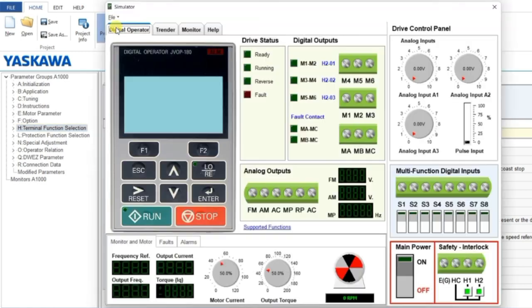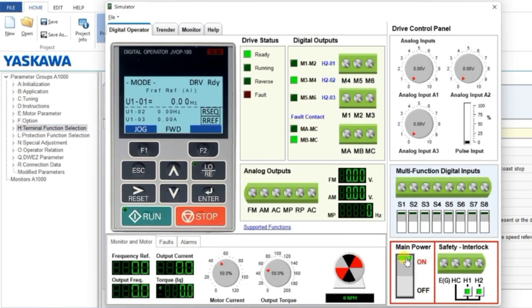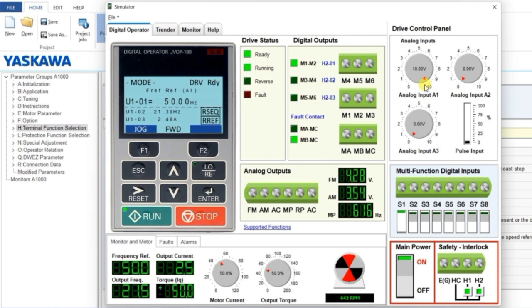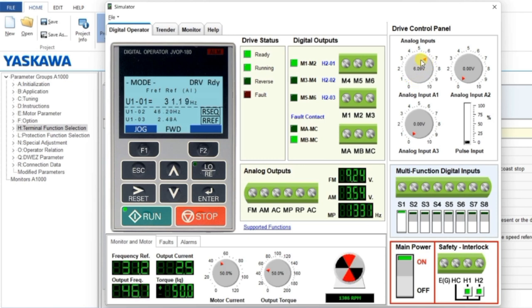Open the simulator and switch on the main power. To run the motor in the forward direction, click on the S1 terminal. However, the motor won't run yet because we also need to provide analog input via the potentiometer. Set it to full 10 volts and the motor will run at 1500 RPM. You can see the direction indicator and the RPM value. By varying the analog input potentiometer, you can adjust the RPM.